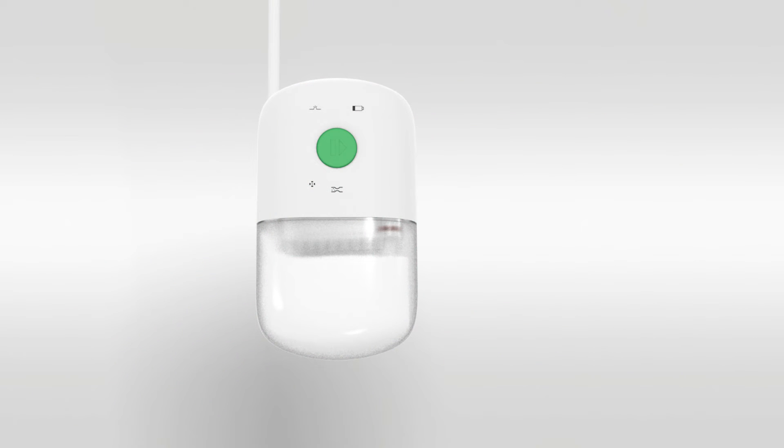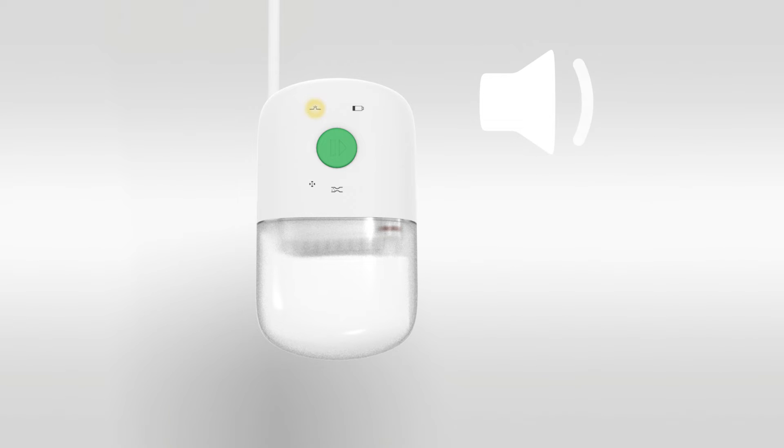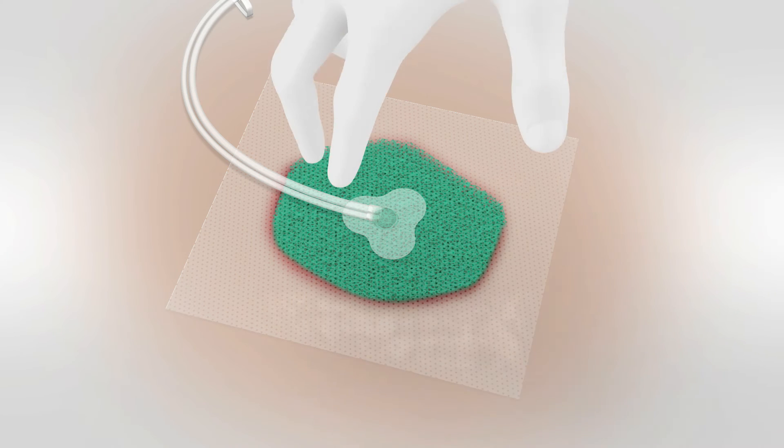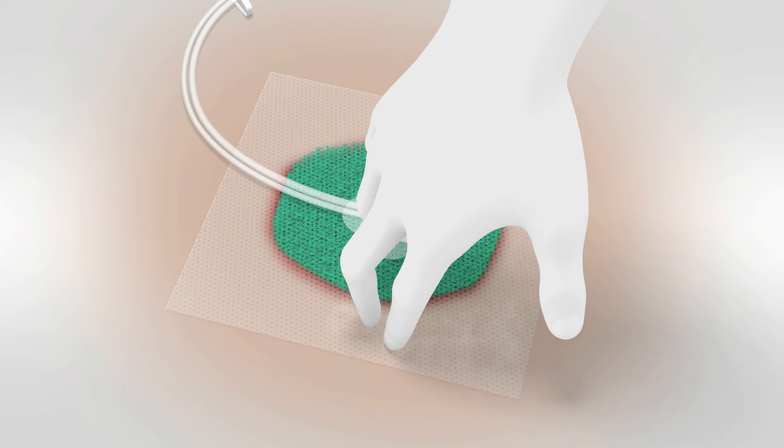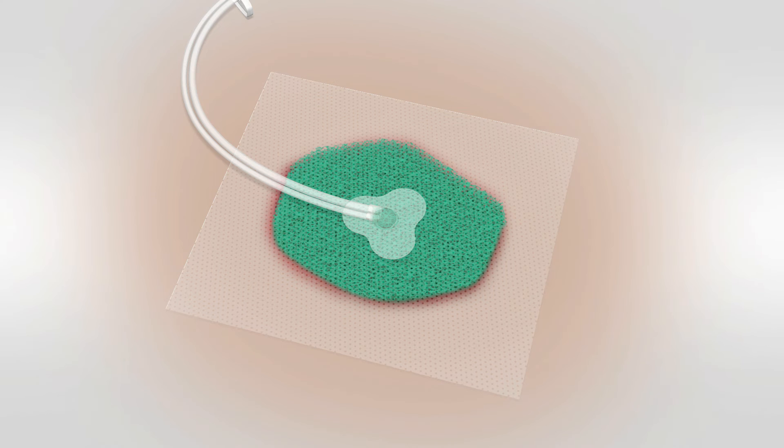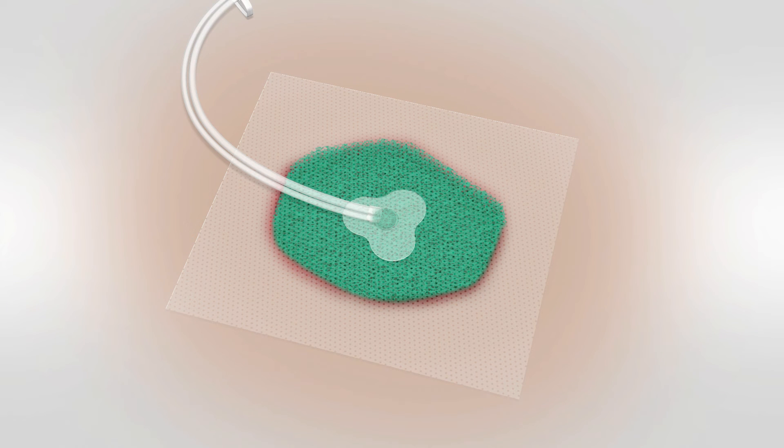If a leak exists at application and negative pressure cannot be established, the device will activate an audible leakage alarm and the light indicator for air leakage will flash once every second. The pump will go into pause mode. If this occurs, adjust the dressing, paying attention to remove any wrinkles in the dressing border before restarting the pump.